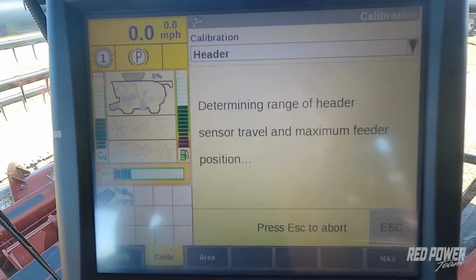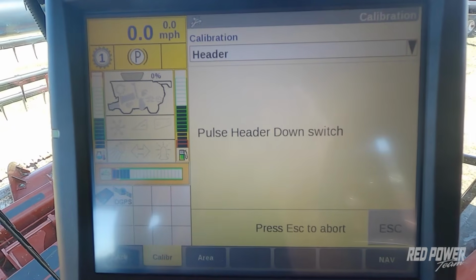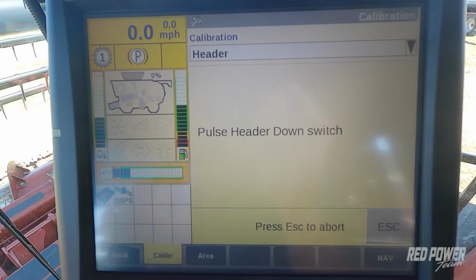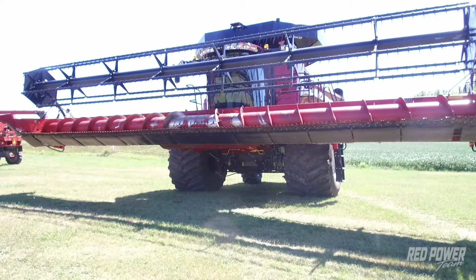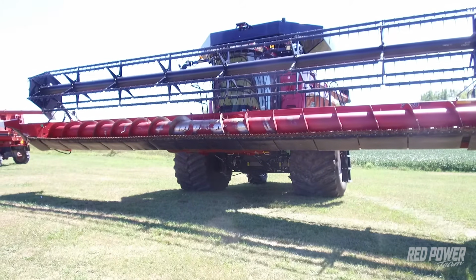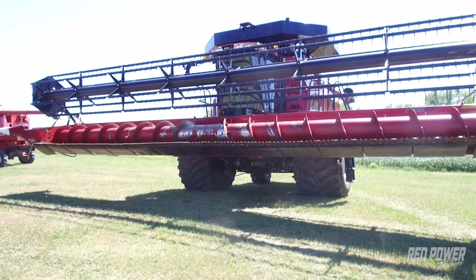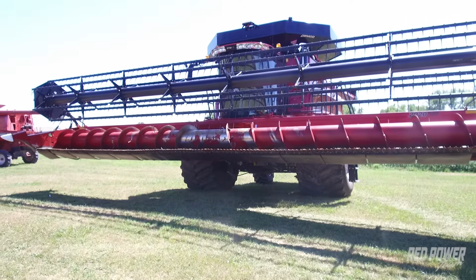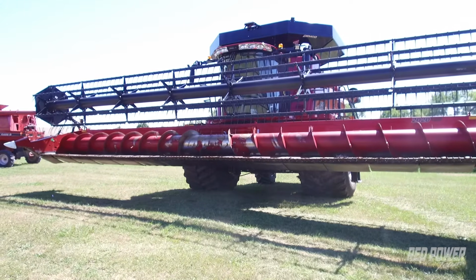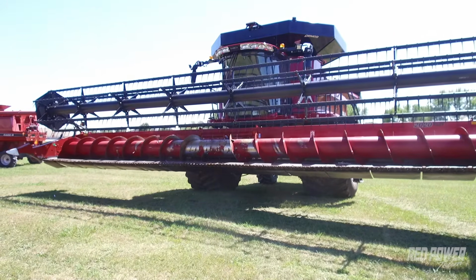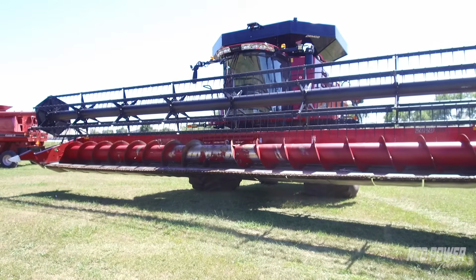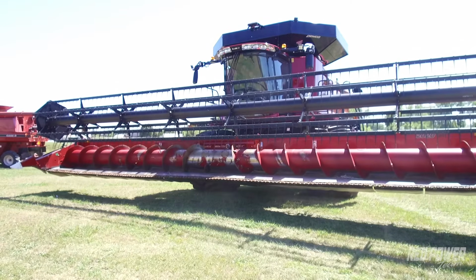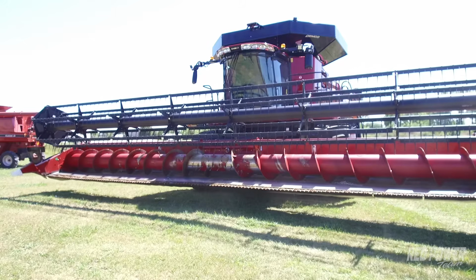Once it gets all the way to the top, it waits a second, and we've completed that step. I press and release my negative button to lower the head down again. This step takes a little bit longer as it's going to try to detect the head weight and determine what pressures are needed to make that head move up and down, so this step takes a little bit of time to complete.